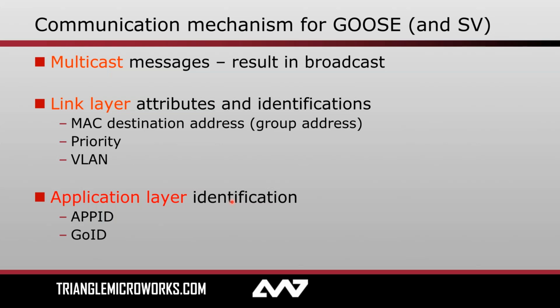Application ID, also set by the user, allows us, if we choose, to group messages that are working towards some common goal. So maybe I have a group of GOOSE messages that are all trying to work together, or are necessary to work together, to accomplish a breaker failure scheme. I could assign them an application ID that groups them in that way.